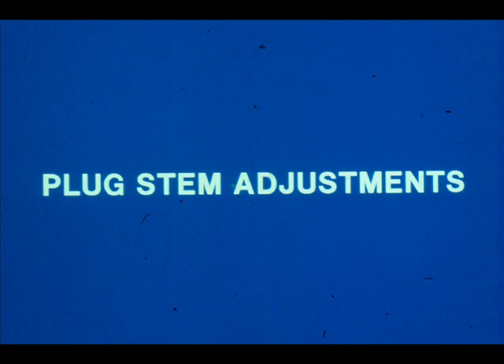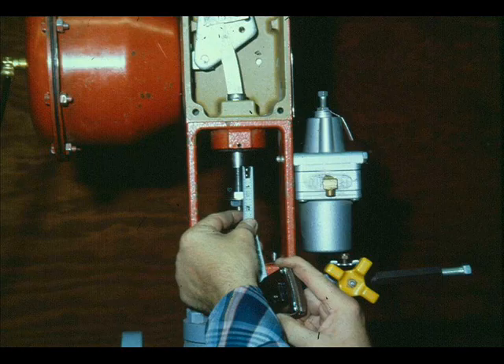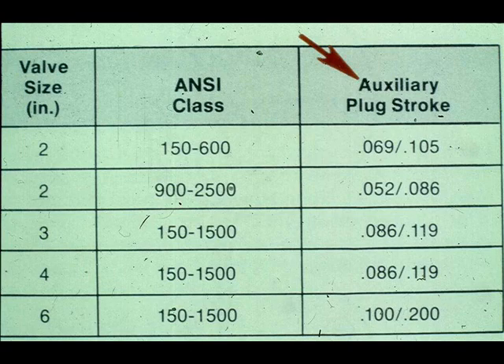Masoneilan recommends the following plug stem adjustment for most of their single and double-seated globe valves and cage valves. For air-to-close valves, separate the plug stem and actuator stem. Push the plug stem down until the plug seats. With no air pressure on the actuator diaphragm, position the lock nuts and indicator disc on the plug stem so that the distance from the top face of the top lock nut to the bottom of the actuator stem is equal to the required valve stroke. For the 41400 series valve, an auxiliary plug stroke must be subtracted from this distance.